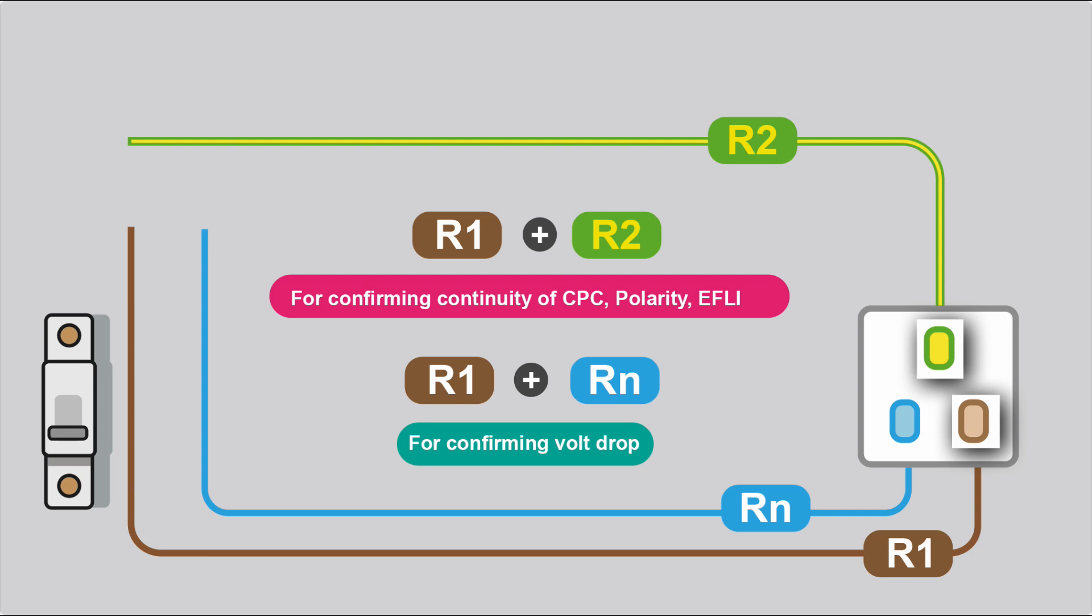So the R1 plus R2 test will be between line and CPC, so it's used for confirming continuity of the CPC, in polarity tests, your earth fault loop impedance. And when you're confirming volt drop, you would test between R1 and Rn, that is between your line and your neutral conductors.